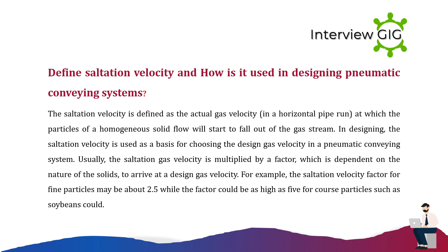Define saltation velocity and how it is used in designing pneumatic conveying systems. The saltation velocity is defined as the actual gas velocity in a horizontal pipe run at which particles of a homogeneous solid flow will start to fall out of the gas stream. In designing, the saltation velocity is used as a basis for choosing the design gas velocity. The saltation velocity is multiplied by a factor dependent on the nature of the solids — for example, the factor for fine particles may be about 2.5, while it could be as high as 5 for coarse particles such as soybeans.